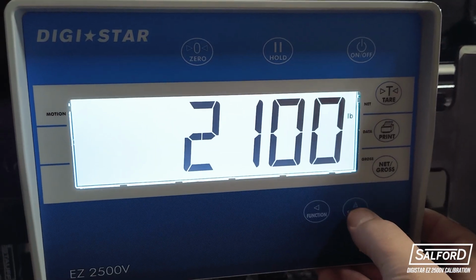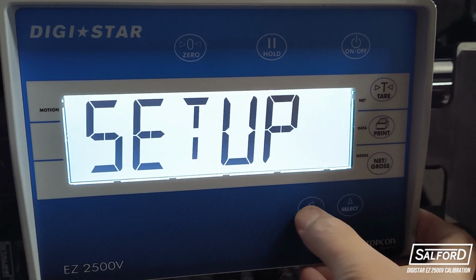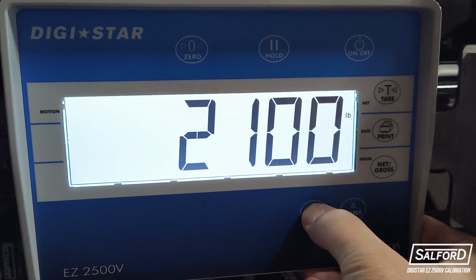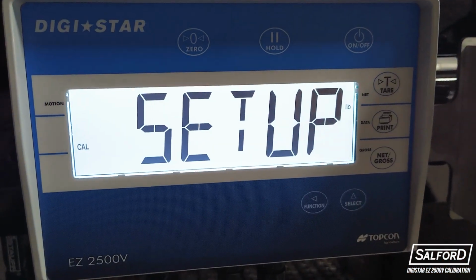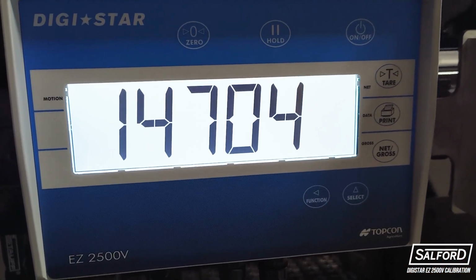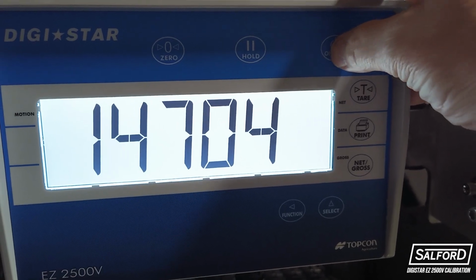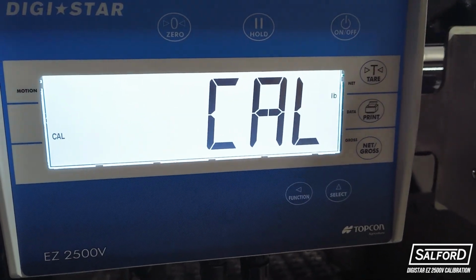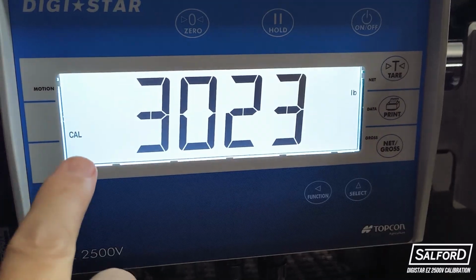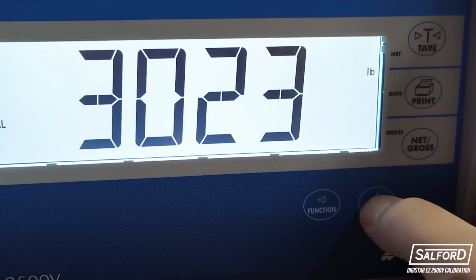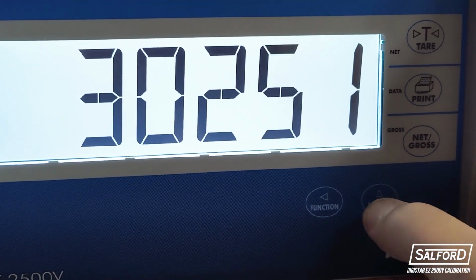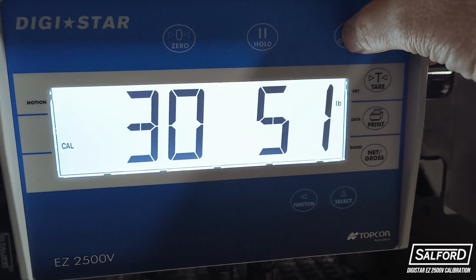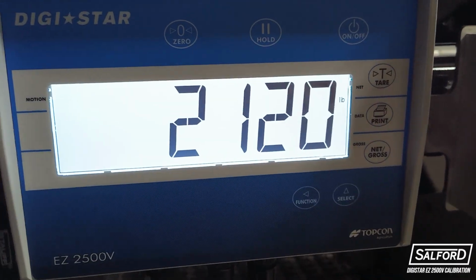To enter the new calibration number, click the select button, then press and hold the function button. The first number displayed is the setup number, which should not be changed. Click but do not hold the on-off button to go to the calibration number. From here, use the select and function buttons to change the calibration number to the new value. Click the on-off button to confirm the new calibration number and the calibration is now complete.